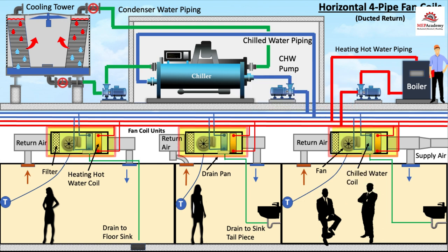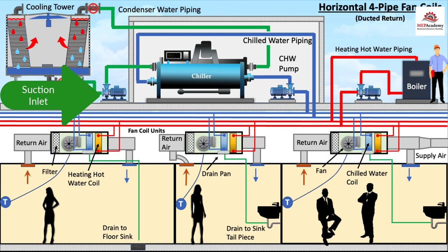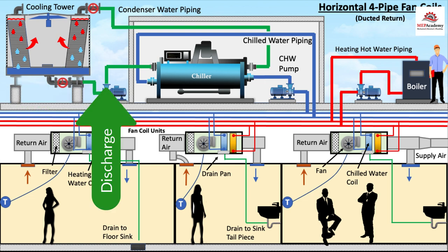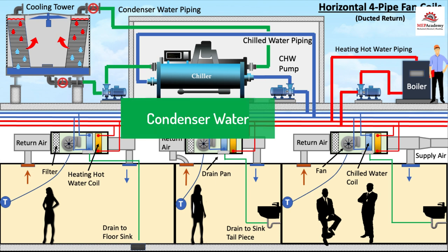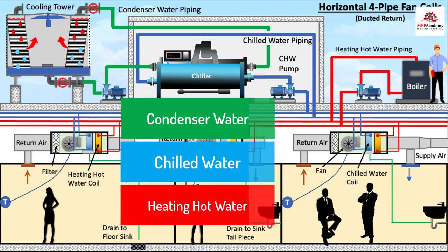And then on the condenser water, you have condenser water end suction pump. It's sucking water from the basin of the cooling tower, through the pump, through the impeller, out the discharge, into the chiller, and then out of the chiller to the top of the tower. So you have three different systems using the centrifugal pumps. You have the condenser water, chilled water, and heating hot water, the three most common systems you'll find in HVAC.